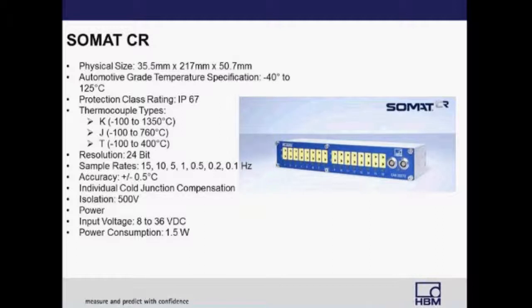Next is the SOMAT-CR, a rugged mobile CAN-based temperature data acquisition module. Engineered to operate within a temperature range of minus 40 to 80 degrees C with an IP67 protection class rating, the SOMAT-CR module allows users to take temperature measurements directly in the most difficult test objects. These modules can be placed in engine enclosures, gearboxes, pumps, power generation systems, and many industrial applications. Its modular design reduces installation time, cabling, and test setup while lowering overall product testing costs.